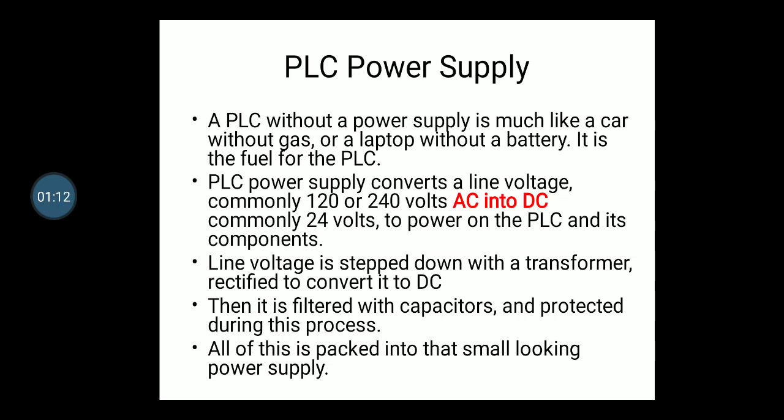A PLC without a power supply is much like a car without gas or a laptop without a battery, right? It is the fuel of the PLC, because if there is no power supply, there are no advantages of PLC. There is no use of PLC basically. The PLC power supply converts a line voltage, commonly 120 or 240 volt AC, into DC, commonly 24 volt, to power on the PLC and its components.